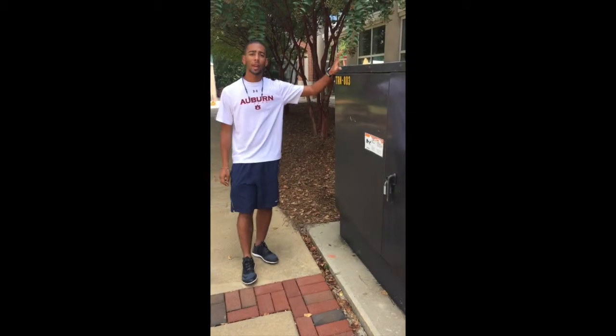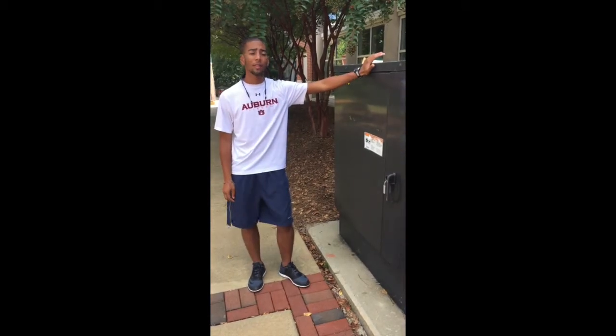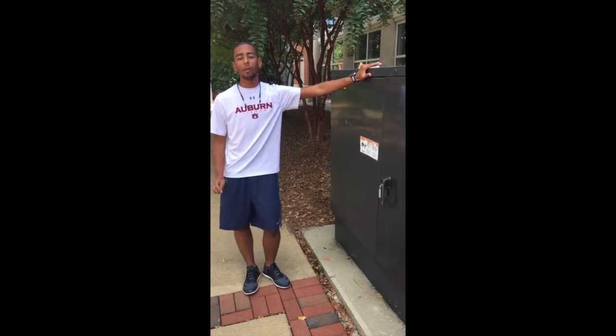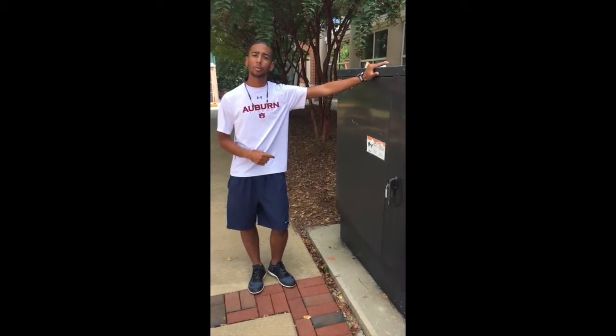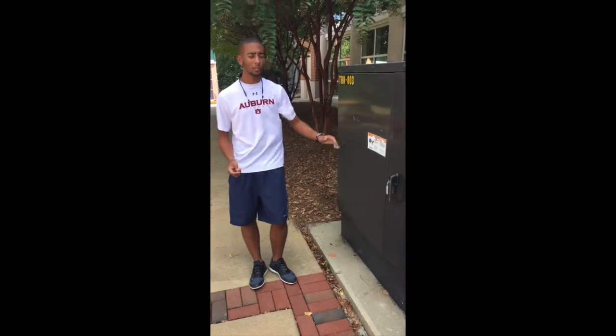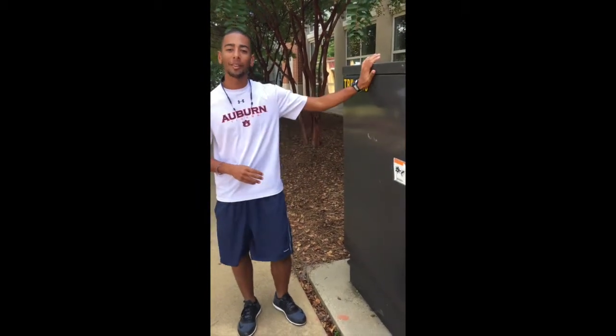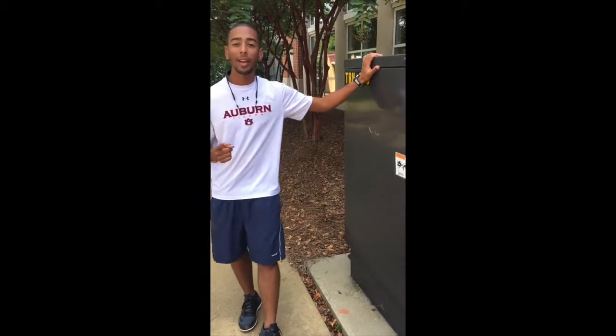Once at the transformer, you can have two types of transformers. Ones that sit above ground on a concrete pad like so, or one that is below ground, which would require more excavation. 480 volts of electricity is run from this transformer to the building by excavating and laying conduit underneath the building through the concrete pad and stubbed up at the main distribution panel.